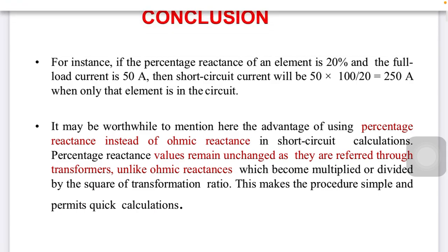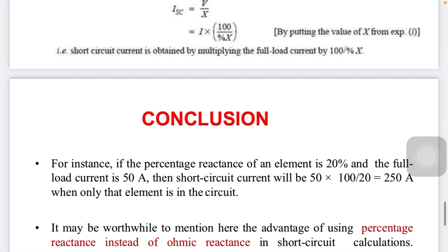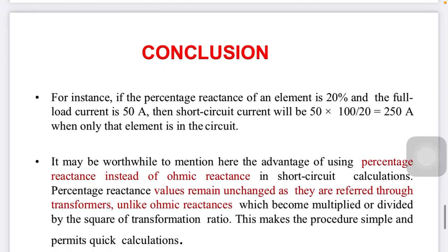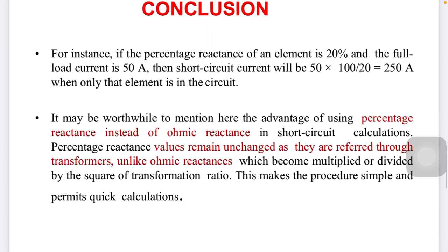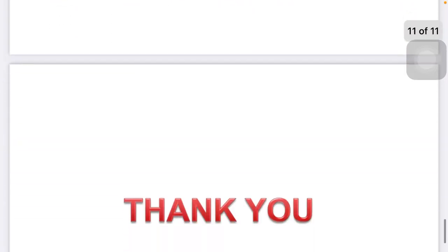It is worth mentioning the advantage of using percentage reactance instead of ohmic reactance. The value remains unchanged when referred through a transformer, unlike ohmic reactance which must be multiplied or divided by the square of the turns ratio (N²). This makes the procedure simpler and enables quicker calculations. Thank you.